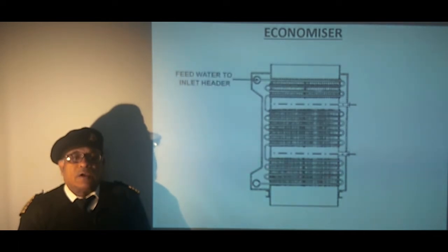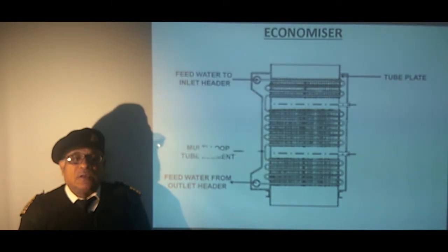We have the feed water inlet header. Here we have feed water from outlet header. This is the tube plate to which these coils are attached. We have the multiple loop tube elements. We have the expansion ring which facilitates the expansion of the multi loop tube element. The anchor collar. The anchor collar is on the other side of the tube plate which holds the multi loop tube element in place.